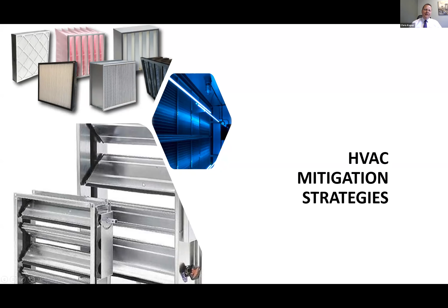Borrowing from my time designing HVAC systems for hospitals, one of the requirements we need to address in HVAC design was pressurization relationships between adjacent spaces. Basically, certain rooms within a healthcare facility should be positively or negatively pressurized with respect to their adjacent areas. Positively pressurized spaces are usually designed to protect the patient, clean supplies, or equipment, while negative pressure is typically used to contain an airborne contaminant within a given space.